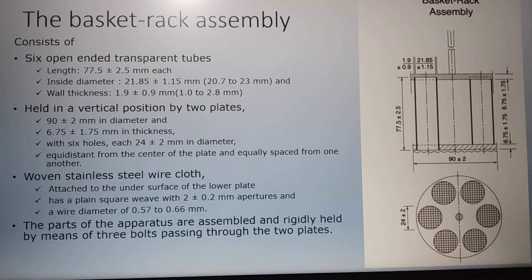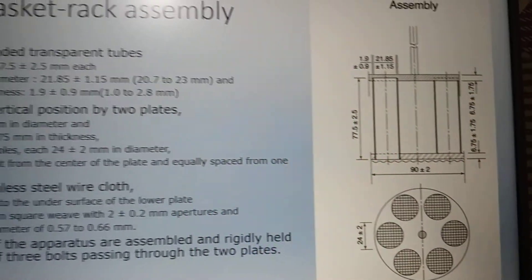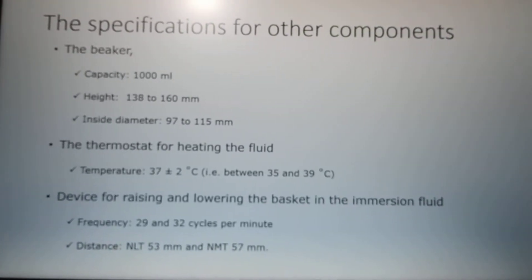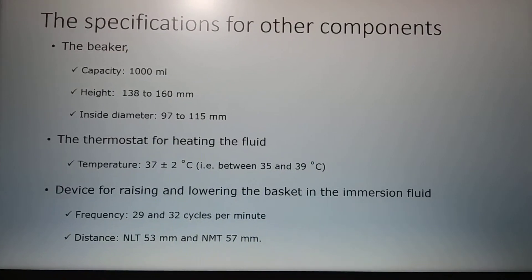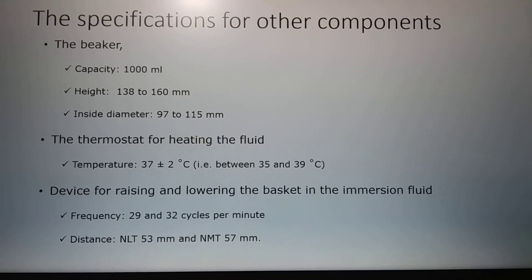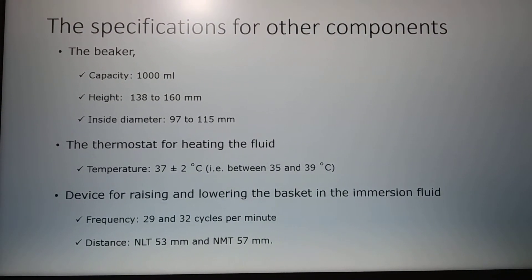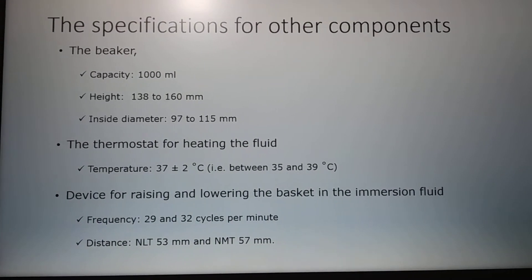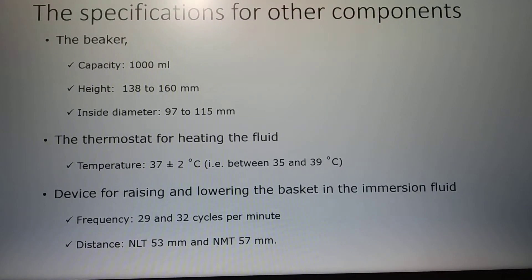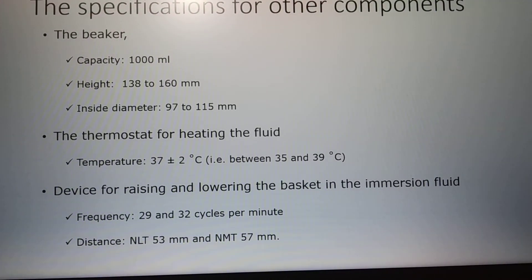You can see all dimensions given in the picture. Specifications for the remaining components are also given in the USP. The beaker has a one-liter capacity; the height of the beaker should be 138 to 160 mm, and the inside diameter is 97 to 115 mm. There is a thermostat which should be capable of maintaining the temperature of the fluid inside the beaker at 37 plus or minus 2 degrees Celsius.